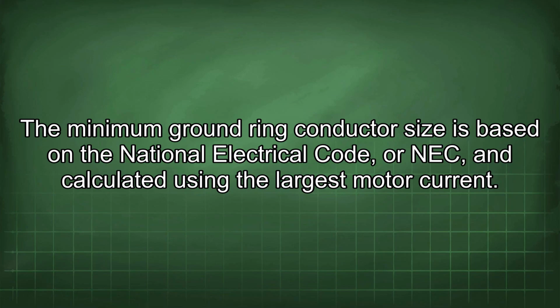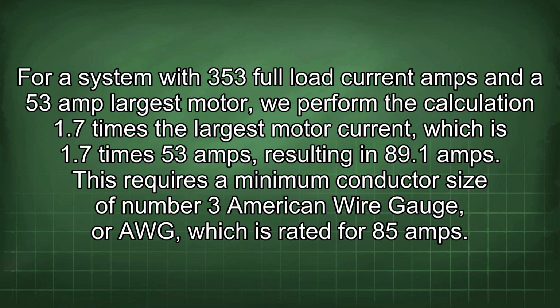The minimum ground ring conductor size is based on the National Electrical Code, or NEC, and calculated using the largest motor current. For a system with 353 full load current amps and a 53 amp largest motor, we perform the calculation 1.7 times the largest motor current, which is 1.7 times 53 amps, resulting in 89.1 amps. This requires a minimum conductor size of number 3 American wire gauge, or AWG, which is rated for 85 amps.